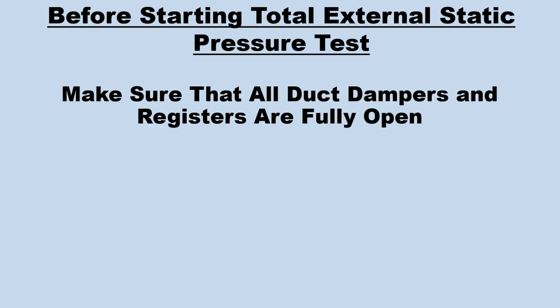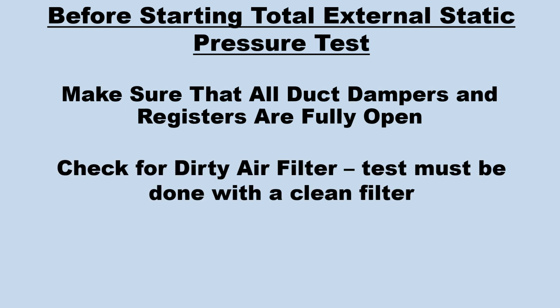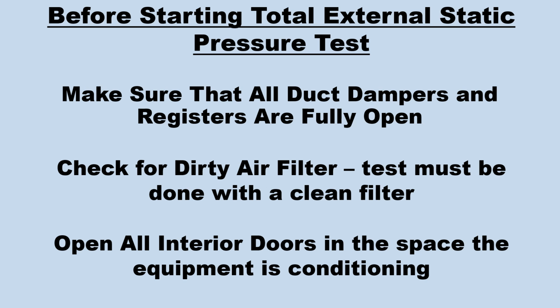Before starting the total external static pressure test, make sure that all the duct dampers and registers are fully open. Check for a dirty air filter. Tests must be done with a clean filter. Open all interior doors in the space the equipment is conditioning, especially in rooms that don't have returns but have doors that close, because a door that's closed on a room that doesn't have a return inside that room is basically acting like a damper and not allowing that room's airflow to circulate in the system.